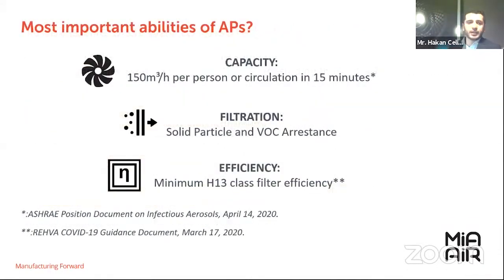So the same declarations also guide us about other specifications, like air circulation rate, efficiency classes, and filtration types. ASHRAE suggests an air purifier capacity of minimum 150 cubic meters per hour per person. For example, if there are 4 people in the same room, the air purifier's capacity has to be minimum 600 cubic meters per hour. And as per ASHRAE, the air exchange rate has to be minimum 6 during COVID. And REHVA is strongly suggesting minimum H13 class HEPA filters in order to fight COVID. So those are the declarations from the authorities.